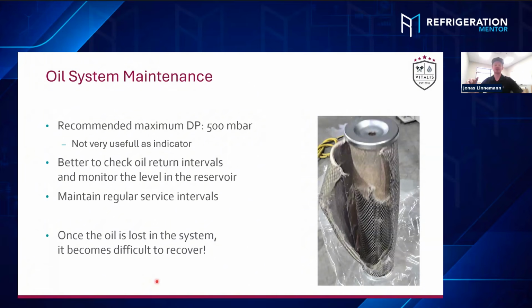We also mentioned that slightly before. Once the cartridge is blown and we lose all the oil into the system, it's gone for a bit. It's very hard to recover that out of the system back to the compressor. Even if you change the oil separator cartridge, you typically notice, because the oil reservoir is empty and the compressor starts to get an oil alarm, and then you can't return the oil anymore. So you need to refill the oil, then you need to start up the system again. And then after a while, once the oil is recovered again, you need to drain it again. So it's important to do the maintenance right and check the function of oil return valves and check the strainers before you lose all that oil.